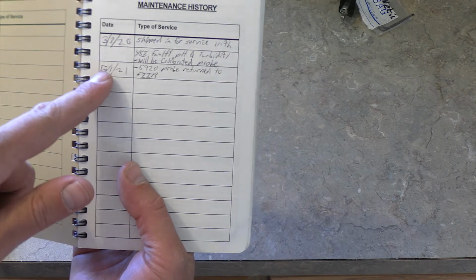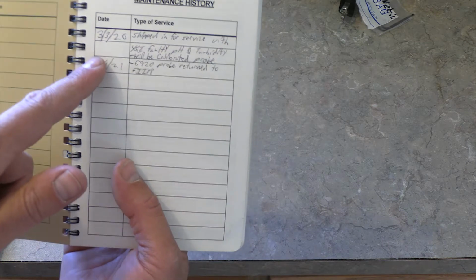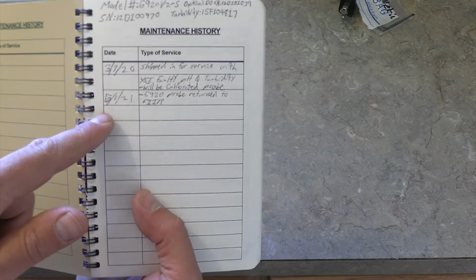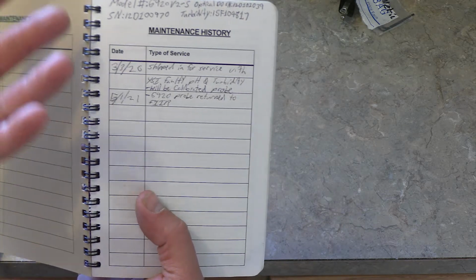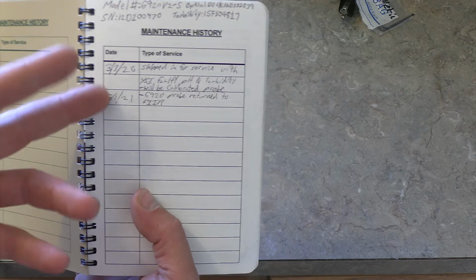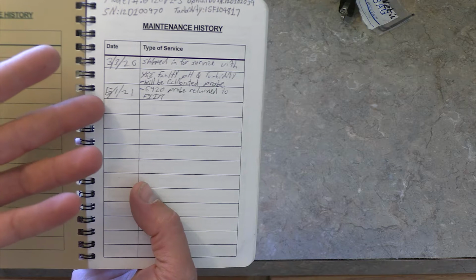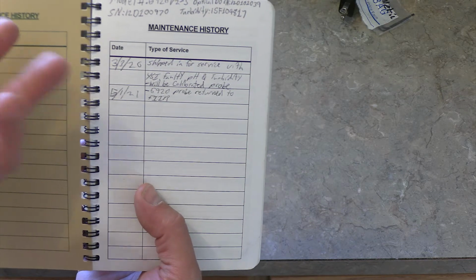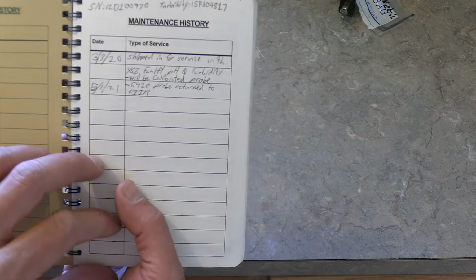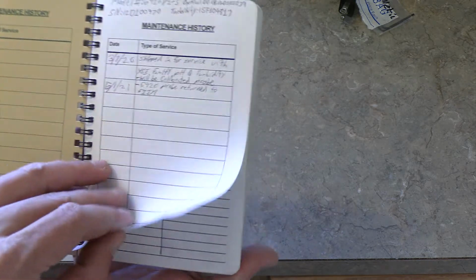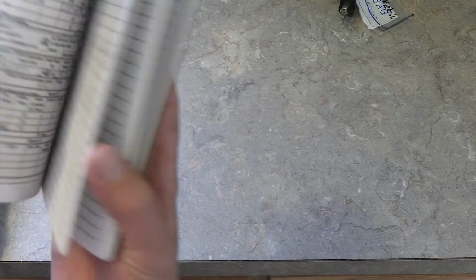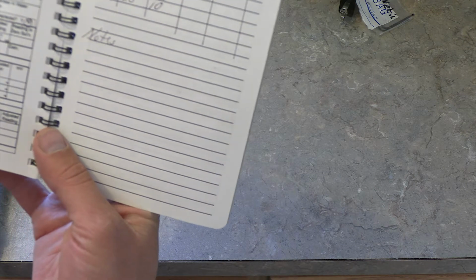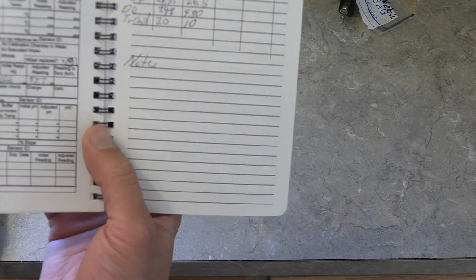I will put in anything at the beginning that has to do with the maintenance of the probe: major maintenance that gets sent off to YSI headquarters or any other maintenance facility, probe replacement or sensor replacement, seal, anything that is requiring larger maintenance not in-house. Okay, so let's go here to one of the most current ones, the last one, say. So this was done last year. This is a partial calibration, so let's go to a full calibration.